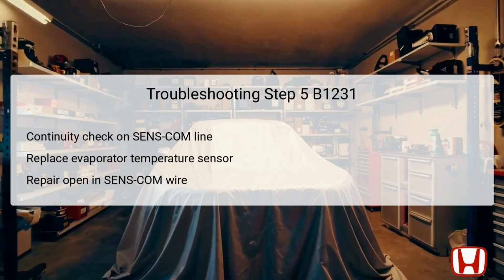Successful continuity indicates that the sensor is functioning properly, while a lack of continuity suggests an open circuit within the sens-com line, prompting the need for repair. If continuity is present, but the issue persists, the technician should consider replacing the evaporator temperature sensor. This thorough check ensures that the primary components of the climate control system are functioning optimally.